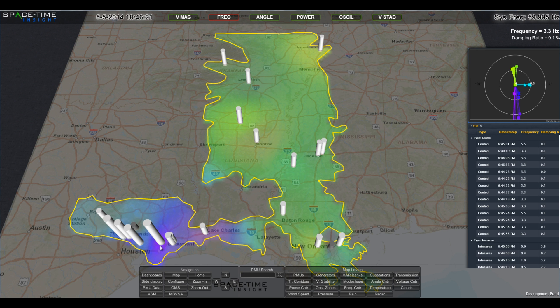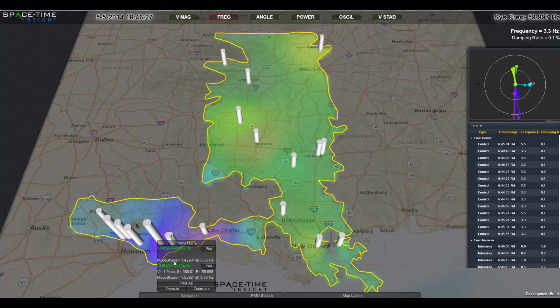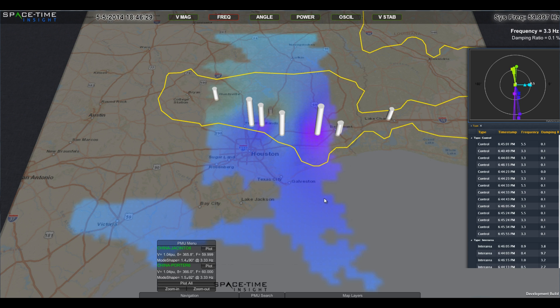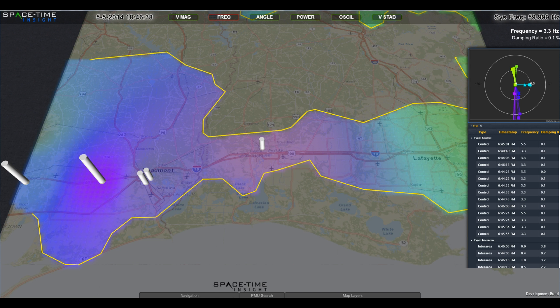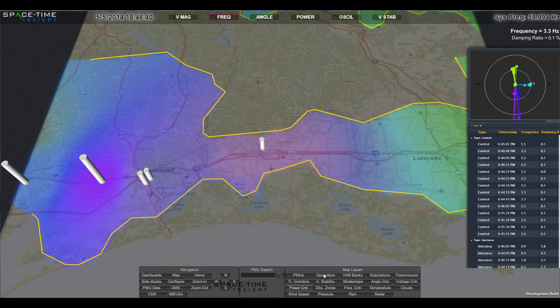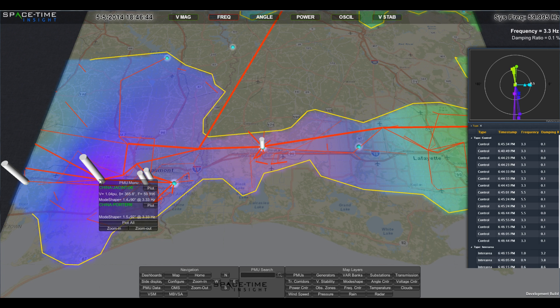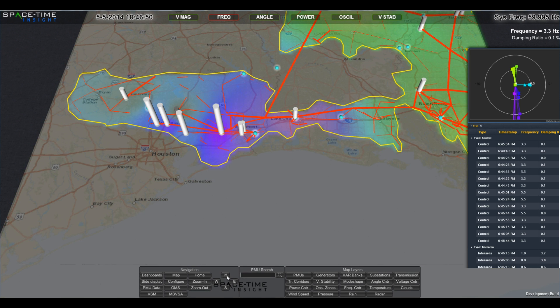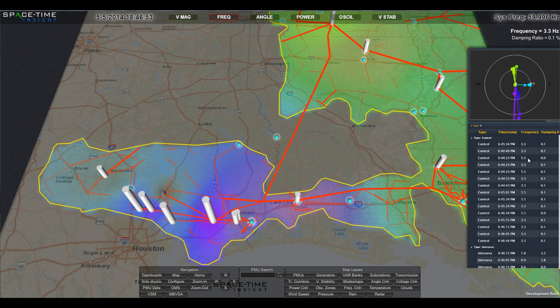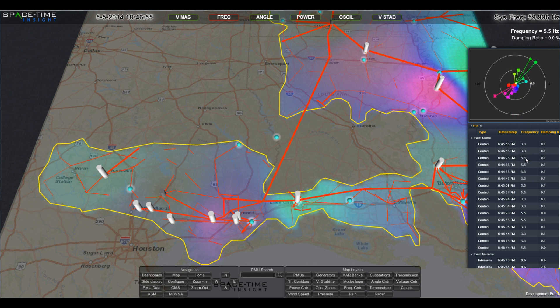The mode shape of the system shows oscillation across the grid, in this case focused on the southwestern arm of the service territory. Viewing the generators and transmission lines in the surrounding area helps pinpoint the source of oscillation. Once the oscillation source is known, it's easy to take corrective action, including collaborating with a generation plant to correct the problem or activating power oscillation dampers.